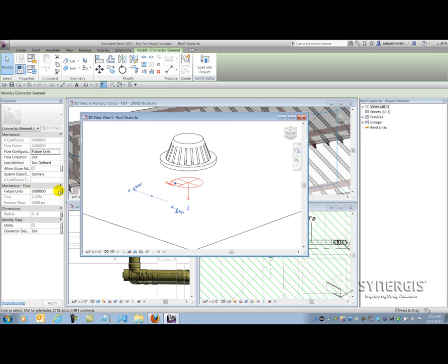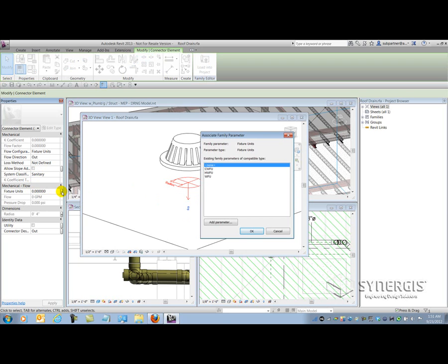The first thing I've got to do is map the property. Clicking the little button to the far right of fixture units, I get three parameters from the family I can pick from because this is a plumbing fixture family. When you pick plumbing fixtures as your category, you get three system parameters called cold water fixture units, hot water fixture units, and waste fixture units. These are type parameters, and I need to be able to input a particular value at each drain because each drain is going to handle a variety of different square footages. These three parameters aren't going to work — I'd have to make multiple types of drains just handling different coverages. It would be an instance-by-instance kind of value, so I need to add a parameter.